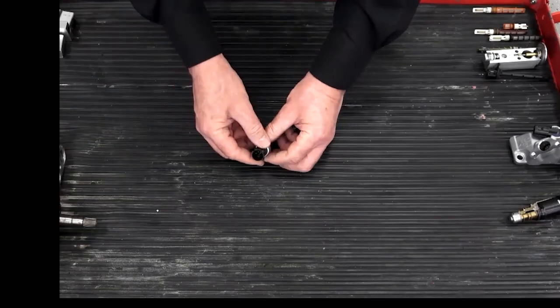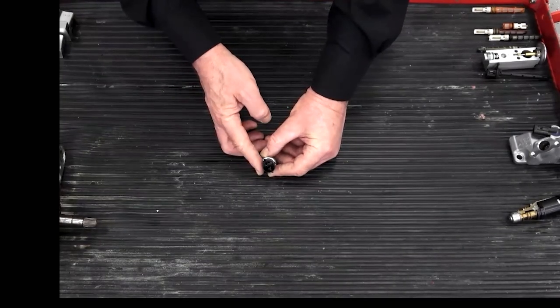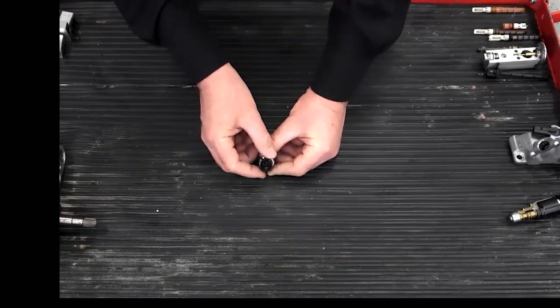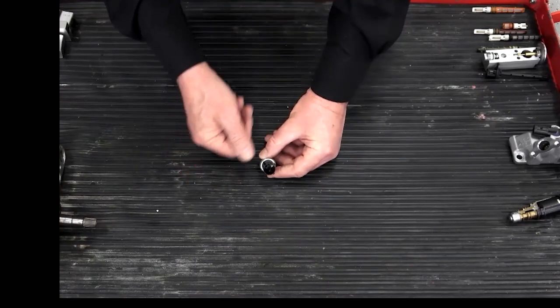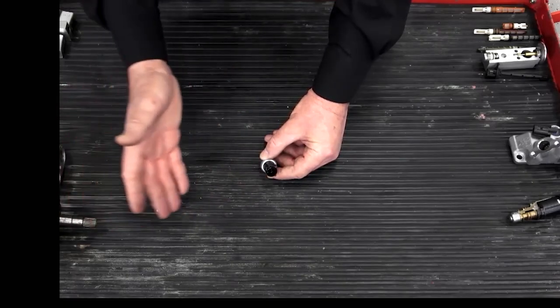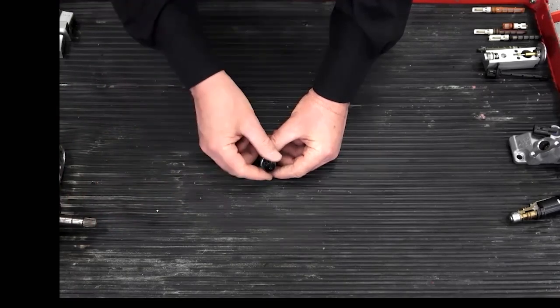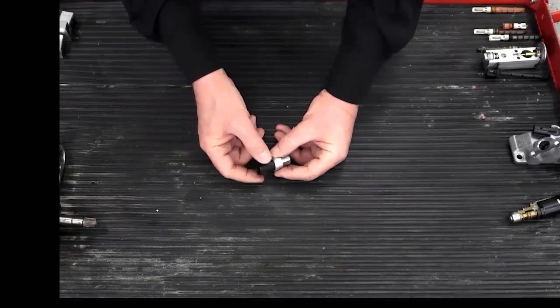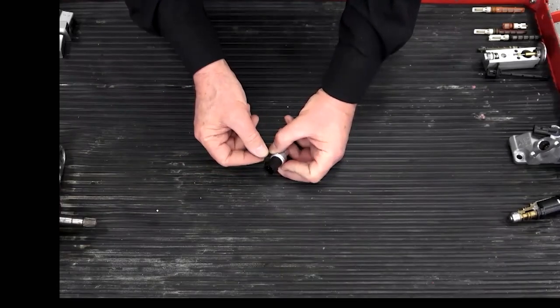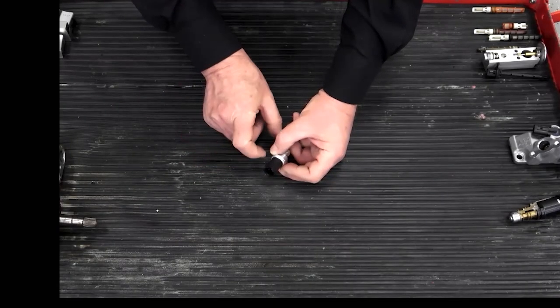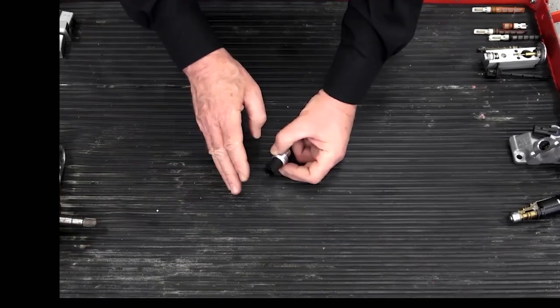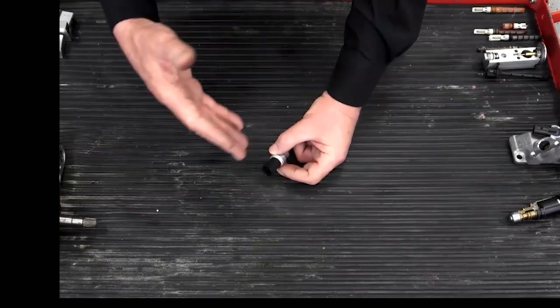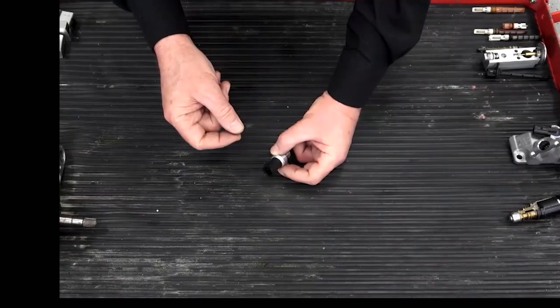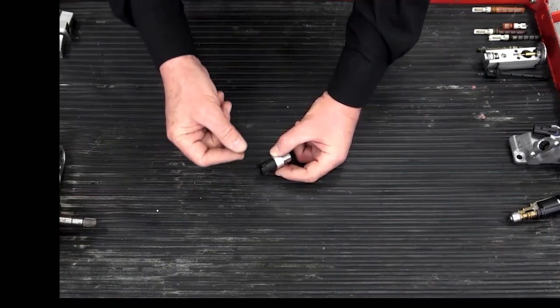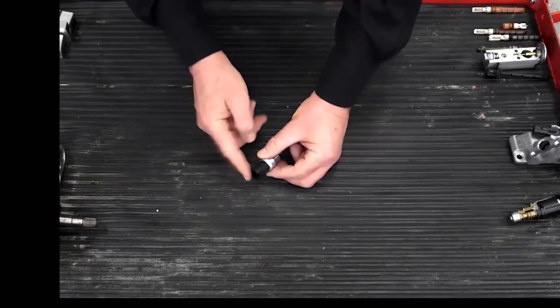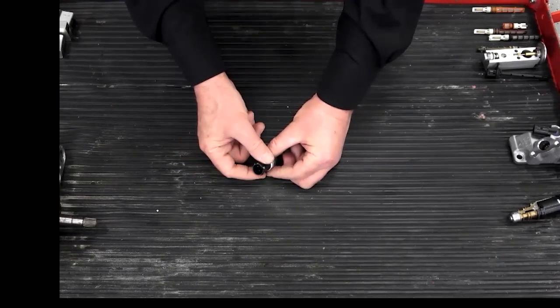And the other issue I see with these pressure transducers is, if the transducer has failed outright, you plug in a scan tool, you're going to see the pressures 500 psi or 0 psi. It's going to be pretty apparent that there's a problem with pressure. The more sneaky failure is where the transducer is shifted. The calibration is shifted 10, 15, 20 pounds, either too high or too low, and that can affect the operation of the compressor and the operation and cutting in threshold for cooling fans. It's very important that this pressure transducer be accurate.